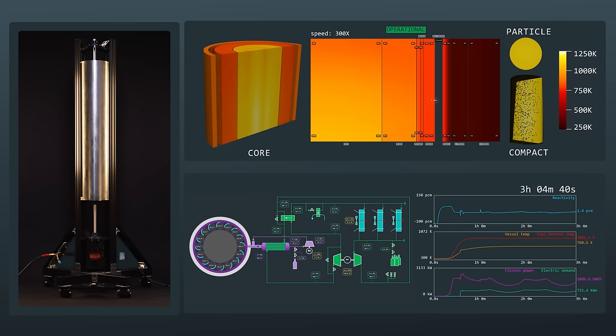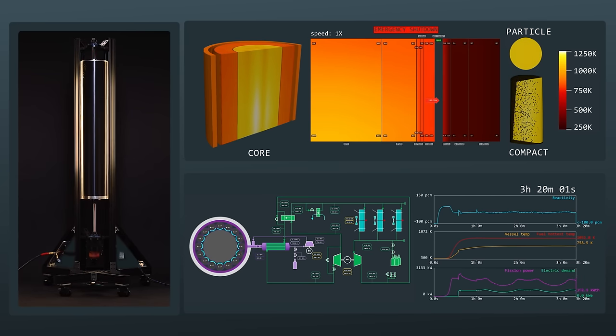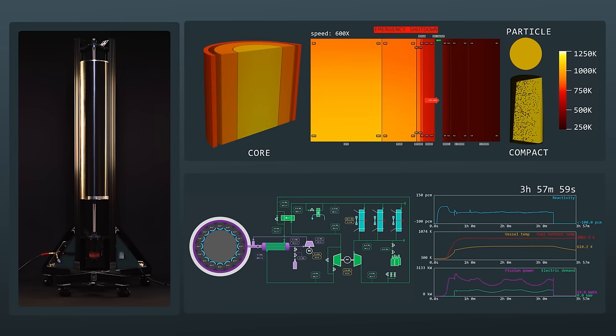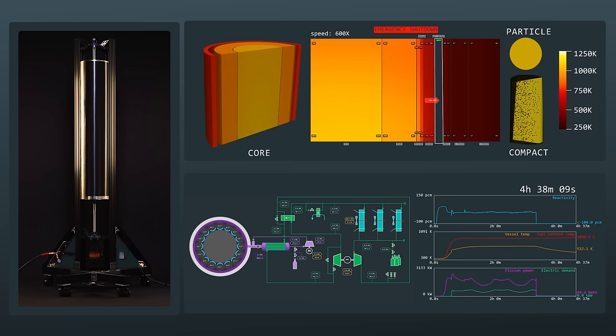Now, SimEngine will inject a helium motor malfunction to demonstrate a pressurized loss of coolant. Under this kind of failure, the temperature of the fuel and vessel are the most limiting safety criteria. As the fault is detected, the control drums shut in to terminate the fission chain reaction and the air jacket opens, allowing heat rejection of the pressure vessel via a natural convection current.